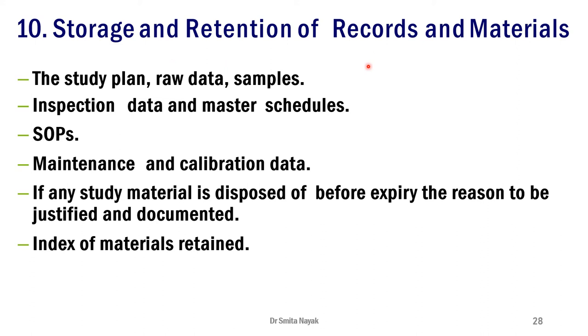All data generated and additional samples — storage samples, reference samples, retest samples — must be properly stored. The last point under good laboratory practices is the procedure for storage and retention of records and samples. What is important to retain includes the study plan, raw data and additional samples, inspection data and master schedules, SOPs, maintenance data, and calibration records. If any material is disposed of due to expiry or any other reason, the reason must be justified and documented. An index of all records and materials should be prepared and available for ready reference.